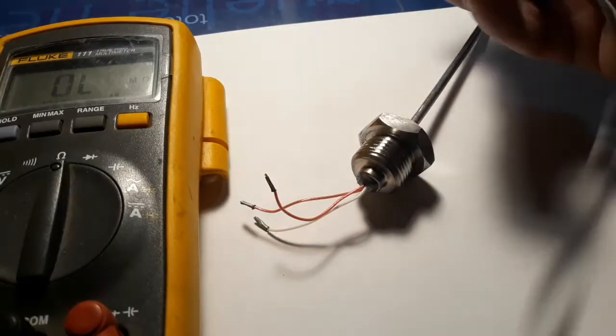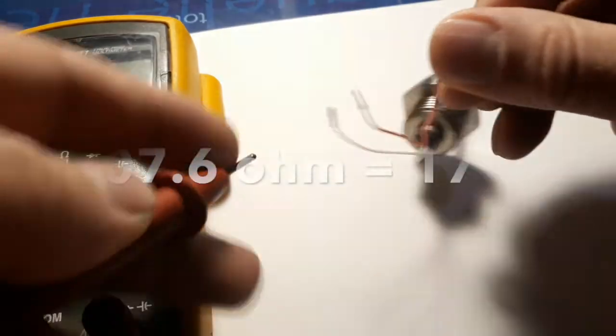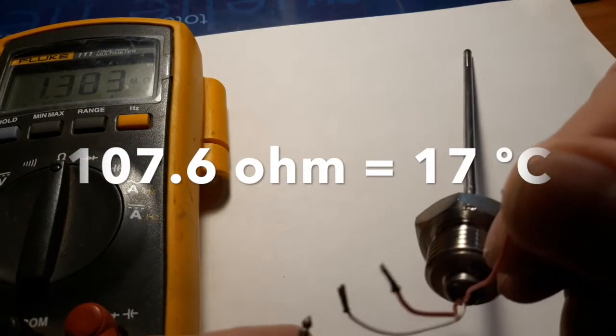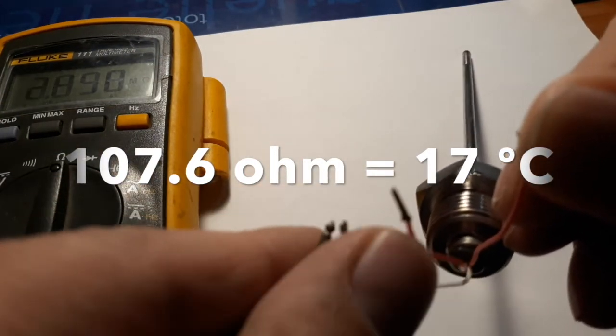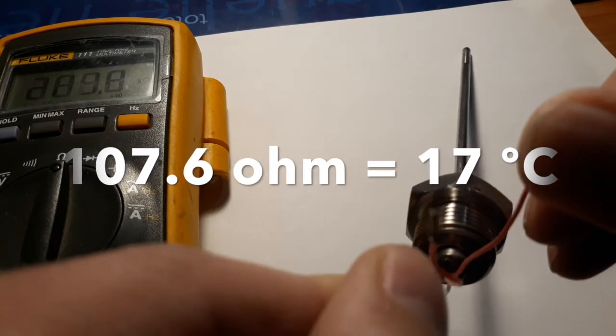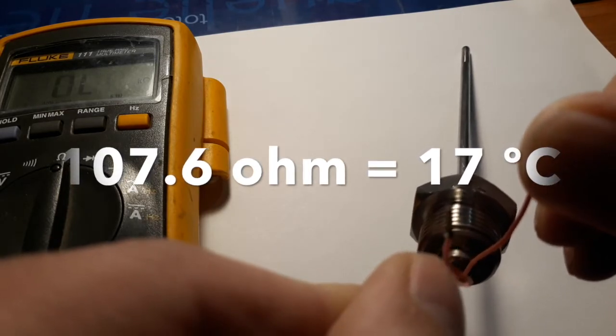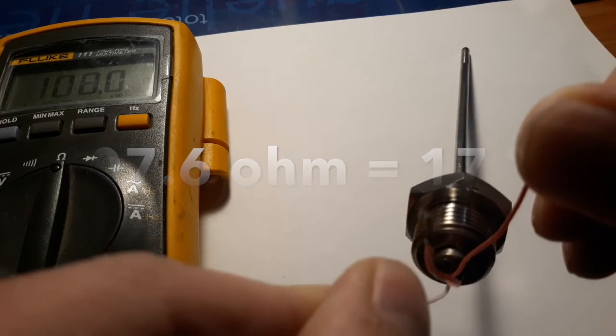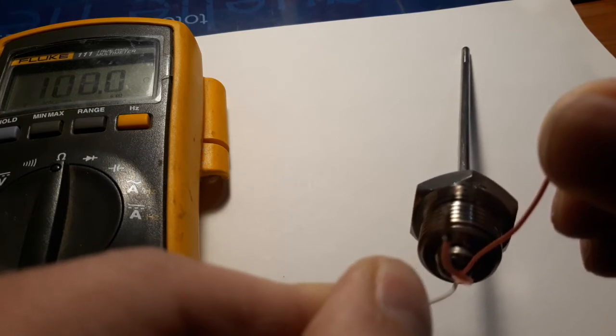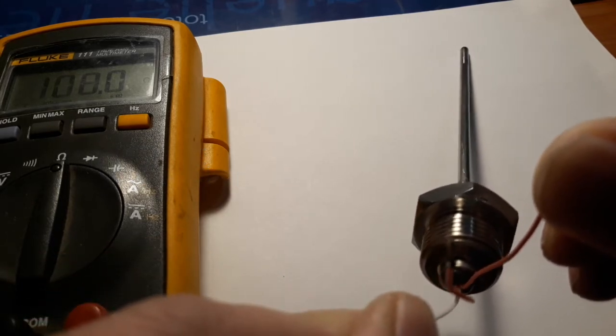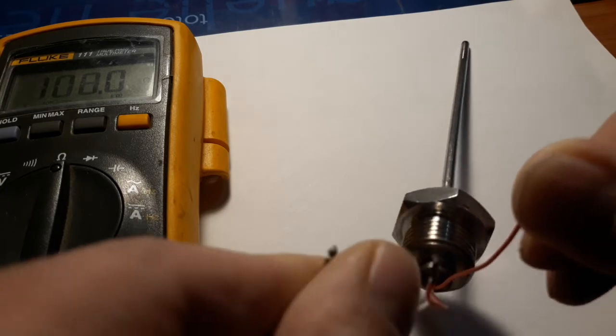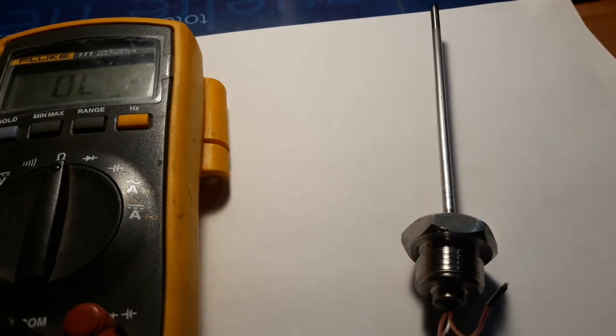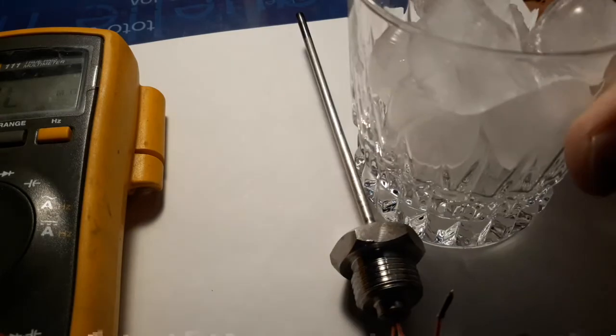With the use of three wires, two red wires connected to the same side of the probe, it is possible to use a normal cable to connect the probe to indicators or controllers. As the probe works with resistance, the two red cables allow the reading equipment to remove the cable resistance from the total resistance. It is equipment widely used in the most diverse industries.